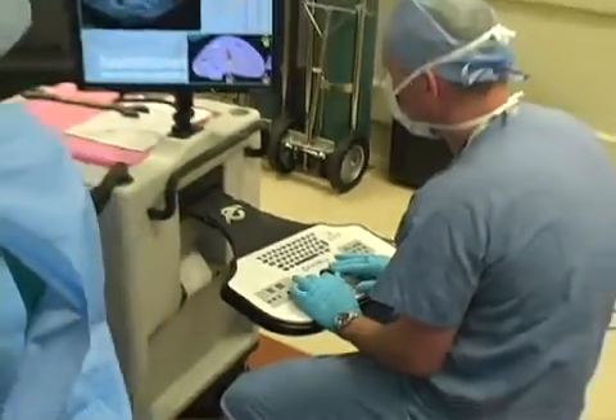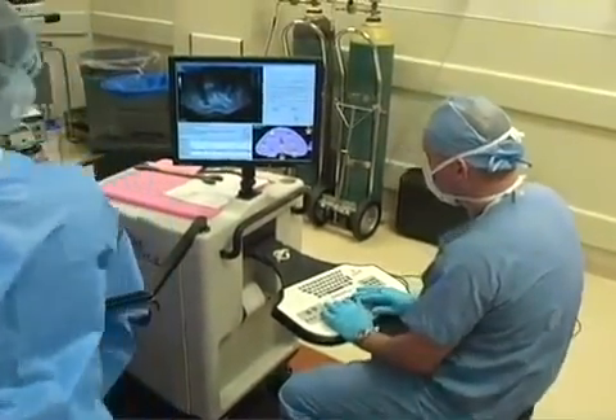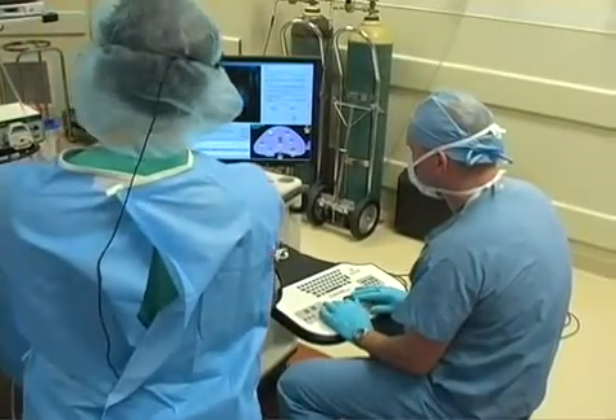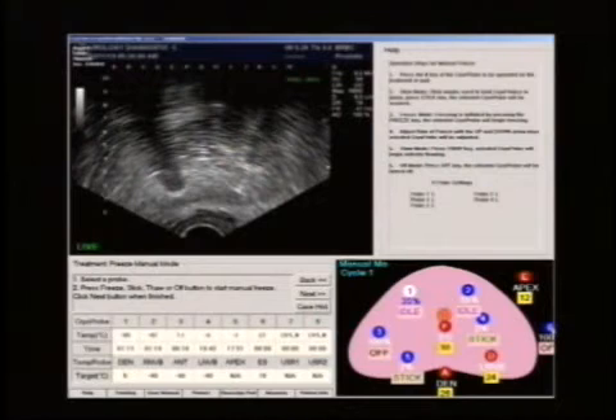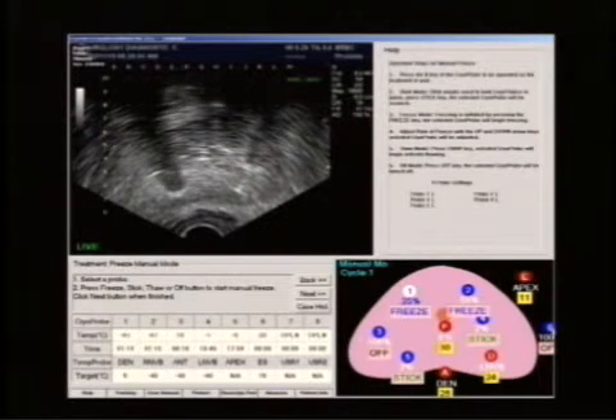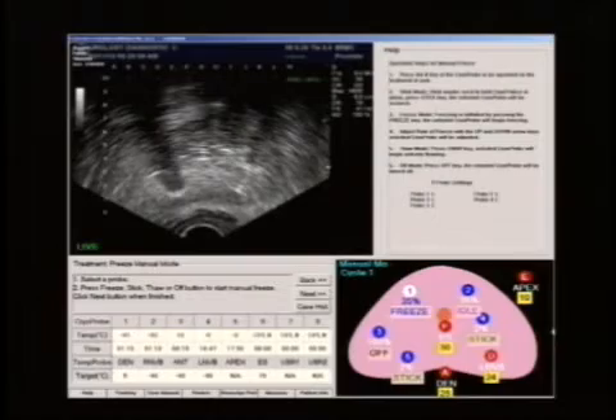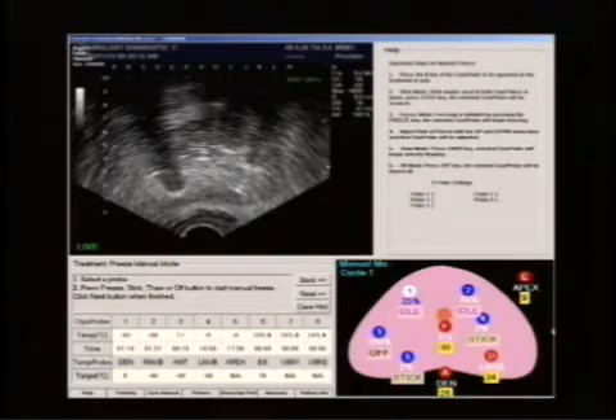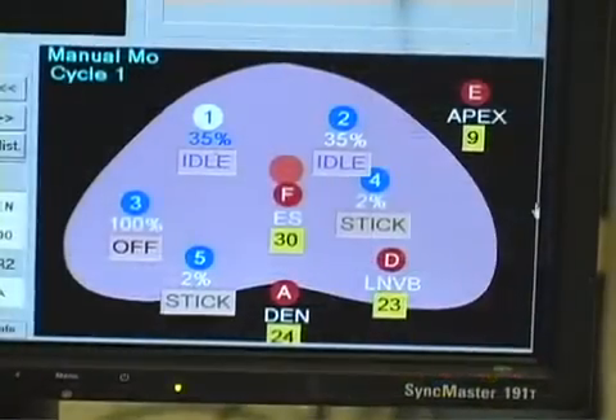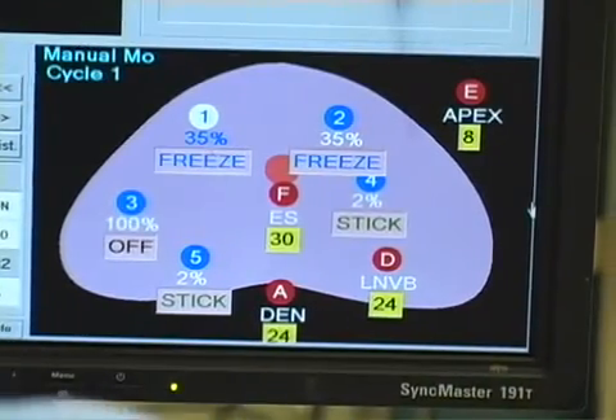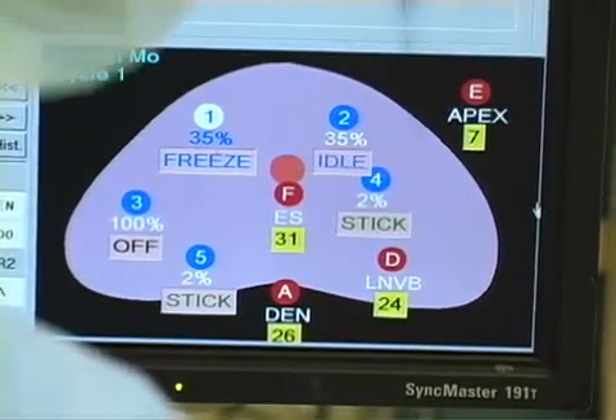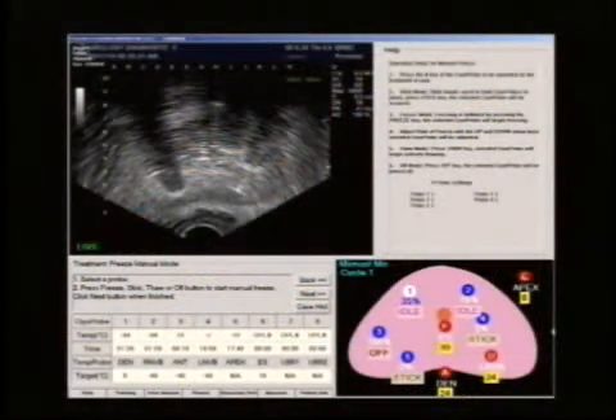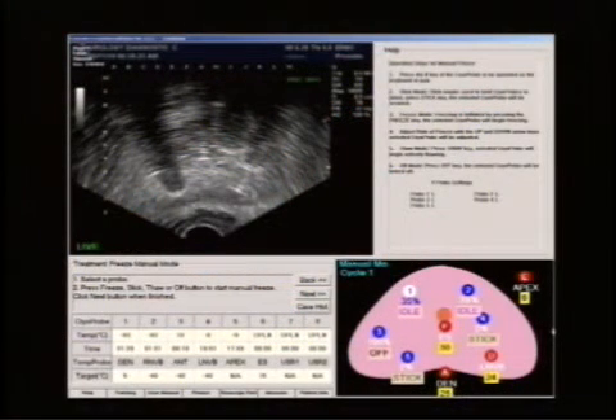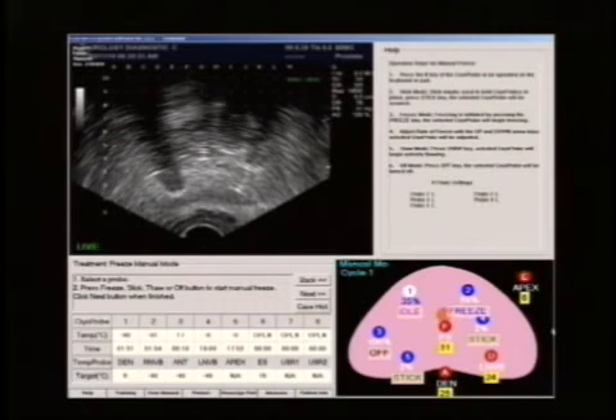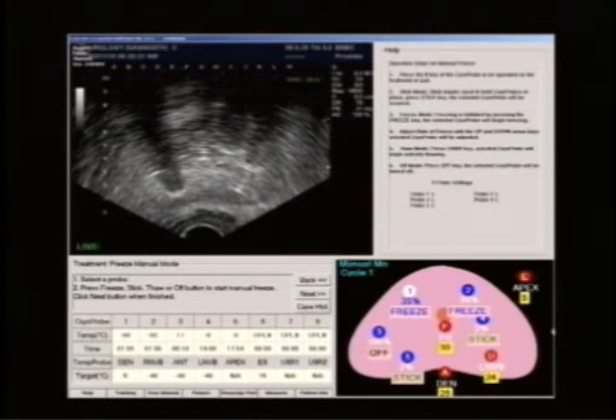Typically, we'll start probes 3 and 4, the next probes to go, when the ice is approaching 3 and 4, or if we see the temperatures on probes 3 and 4 changing, letting us know that the ice is getting close, since these probes can sense the change in temperature. You can actually see that here now in probe 4, which is already down to -7 degrees Celsius. So again, this lets us know that probe 4 is sensing the temperature from probe 2.